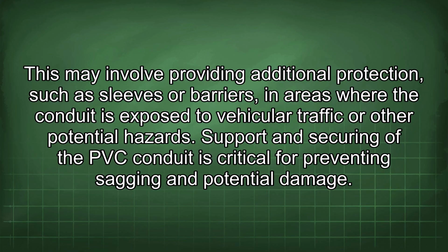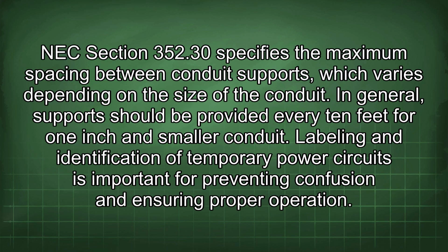Support and securing of the PVC conduit is critical for preventing sagging and potential damage. NEC Section 352.30 specifies the maximum spacing between conduit supports, which varies depending on the size of the conduit. In general, support should be provided every 10 feet for 1 inch and smaller conduit.